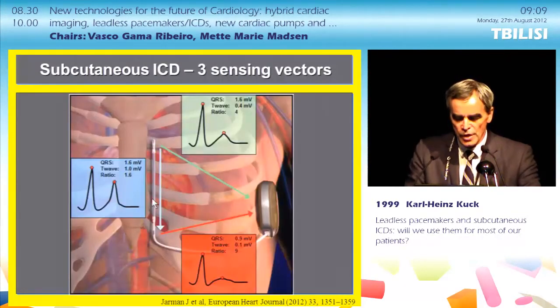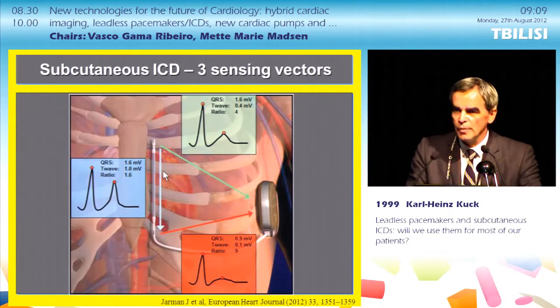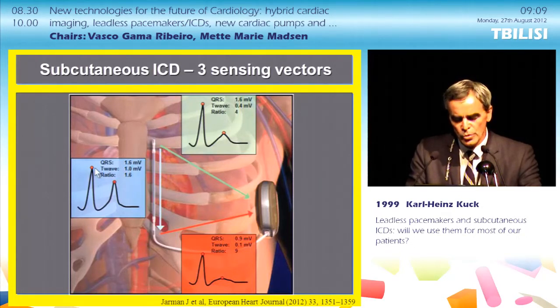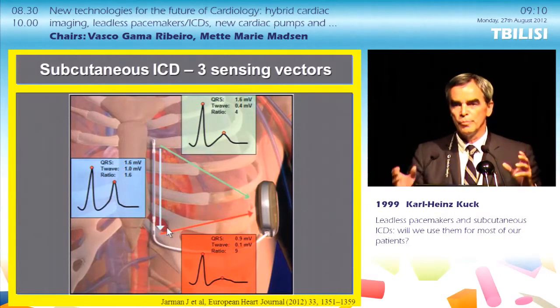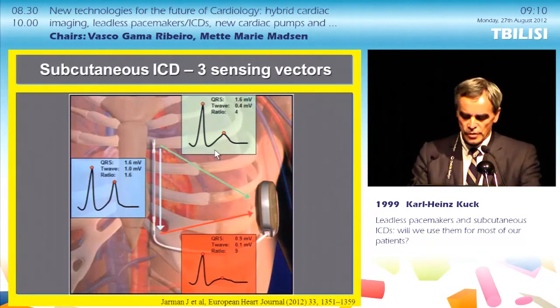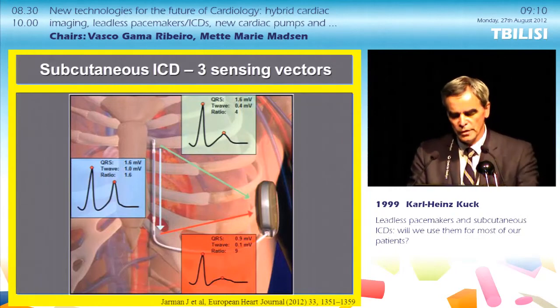Now, as I mentioned before, before the device can be implanted, there are some recommendations that come from the company that you have to do testing, whether the vector, and it's mostly the R to T ratio that counts. And you have to test this ratio, and as you can see in this example, you have 3 vectors: from the distal sensing electrode towards the can, from the proximal towards the can, and between the 2 electrodes. And they are continuously monitoring the R to T ratio before the decision is taken to deliver an impulse.